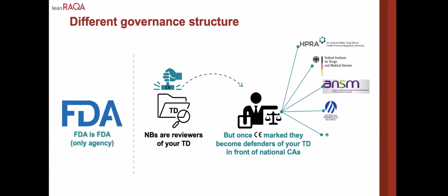Also, with FDA, bringing your product to market is pretty much a one-stop shop. One time you go through, and unless you make changes, you really don't have to do another submission. However, in Europe, the notified bodies will review your documentation every 3 to 5 years, and it has to be maintained in a way that is state of the art, and all your testing has to be updated periodically.